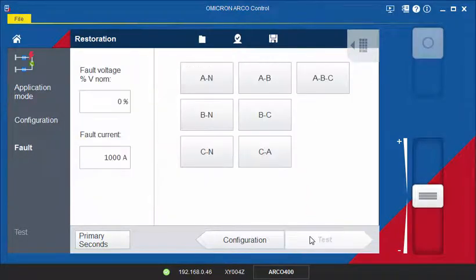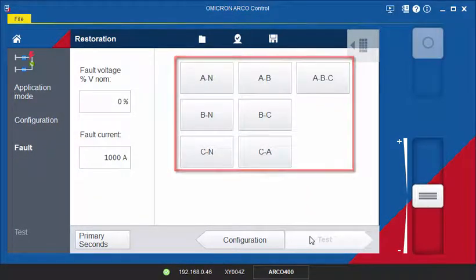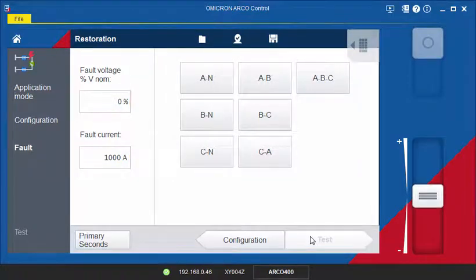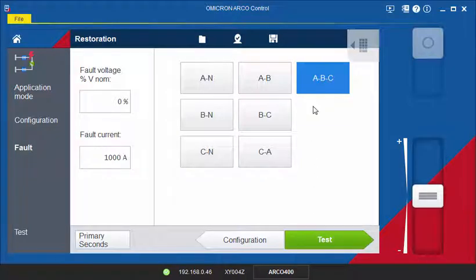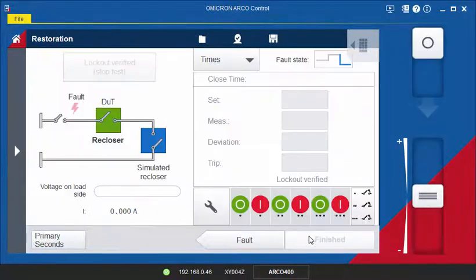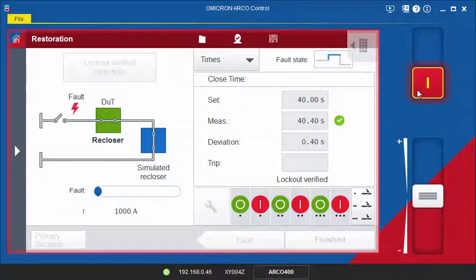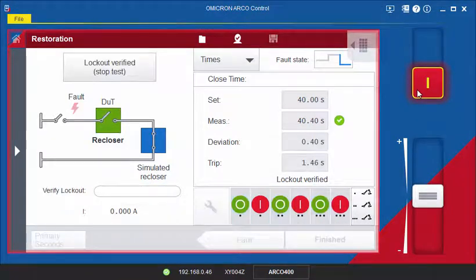On the next page, you will need to specify the fault type, fault current and fault voltage. The fault will be the last state output by the ARCO 400 to simulate the still existing fault. In our example, we assume a three-phase fault. The results of the test are assessed based on the measured close time and the verification of the lockout state at the end of the test.